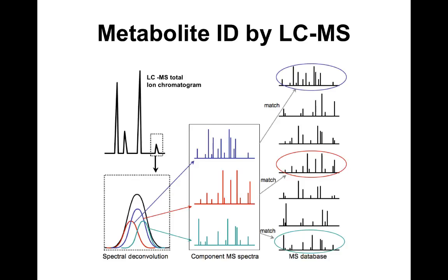All right. Now, LCMS. You'll notice the figure looks almost identical to the figure for GCMS, and in many respects it is. We work with liquid chromatographic outputs. Most peaks from an LC run will have multiple compounds buried under them, and we can collect the ESI-MS or MS/MS spectra for those, and the combination of the ESI-MS or MS/MS spectra can then be matched against the library. And that's how we ultimately identify the compounds.